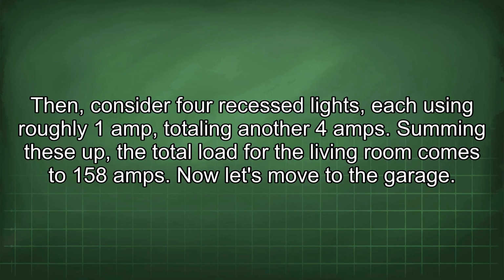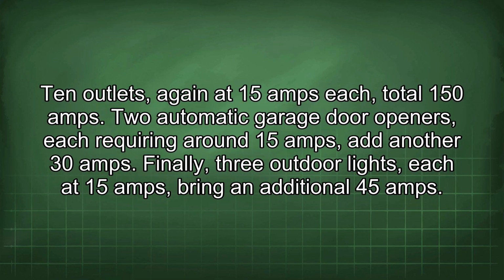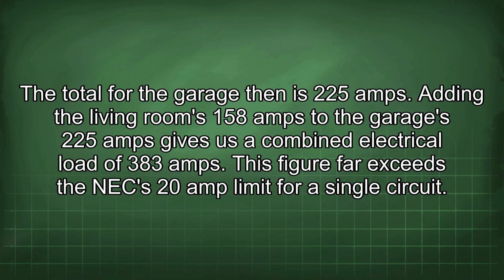Now let's move to the garage. 10 outlets, again at 15 amps each, total 150 amps. 2 automatic garage door openers, each requiring around 15 amps, add another 30 amps. Finally, 3 outdoor lights, each at 15 amps, bring an additional 45 amps. The total for the garage then is 225 amps.